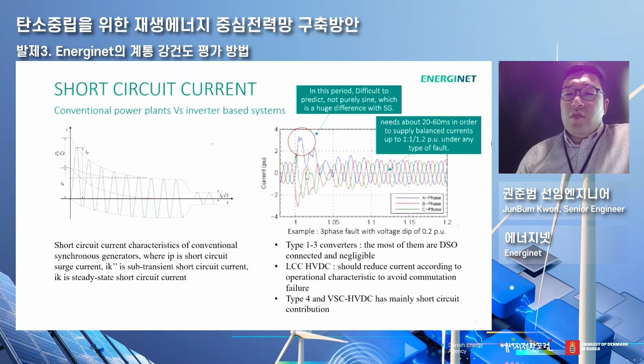In the beginning, when there is a short circuit current, the first peak is very difficult to predict because it happens at the microsecond stage. With a synchronous generator, the sinusoidal shape is not happening, so it shows a totally different tendency compared to a converter, and it is also influenced by various other factors. So the area that we focus on is what happens after that. In this period, it's difficult to predict, not a pure sine wave, which is a huge difference with SG. There is a need for about 20 to 60 milliseconds to supply balanced current up to 1.1 to 1.2 pu under any type of fault.